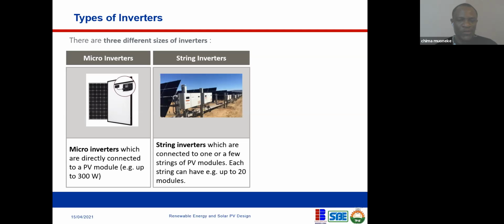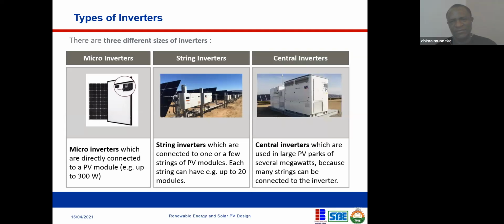Each string can have up to 20 modules, as the case may be. This is the size of inverter connected at the string level. Then you have a central inverter, used in large PV parks of several megawatts, because many strings can be connected to it. You can connect as many solar modules as possible, all to a single inverter. So these are the 3 sizes of inverter we have.